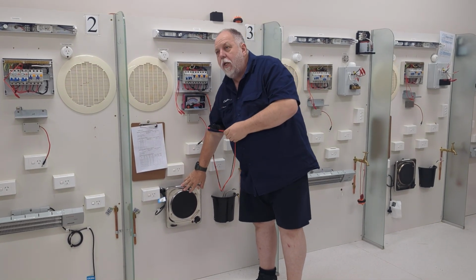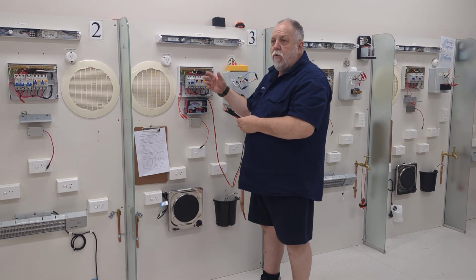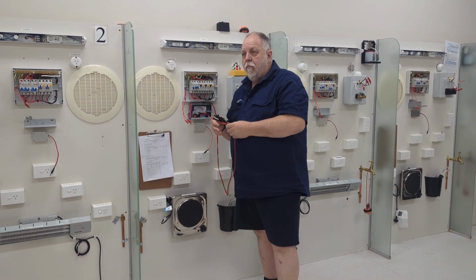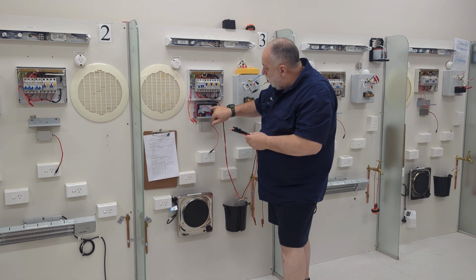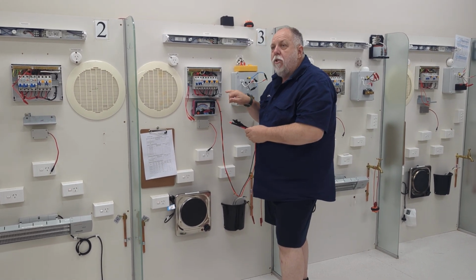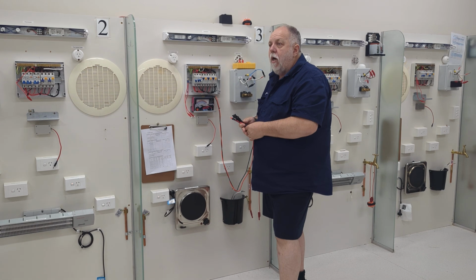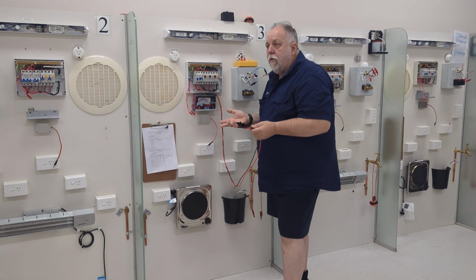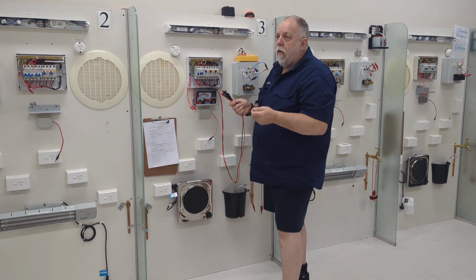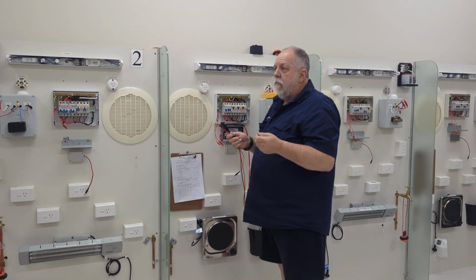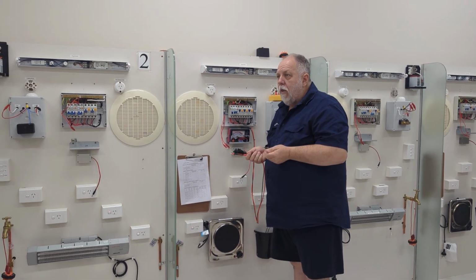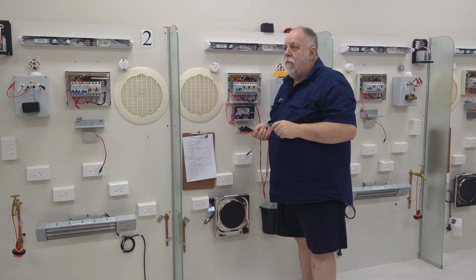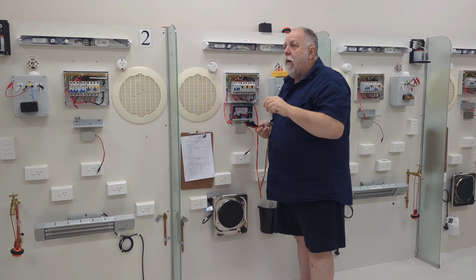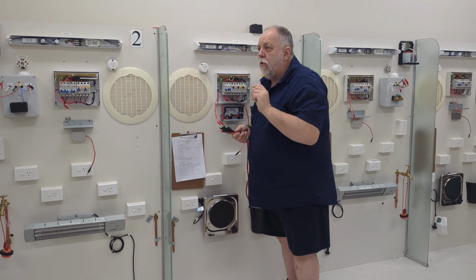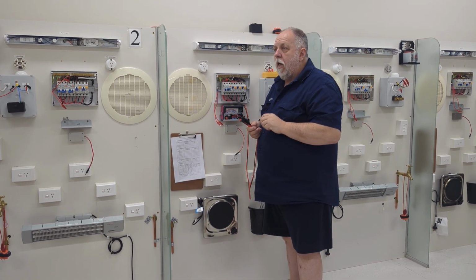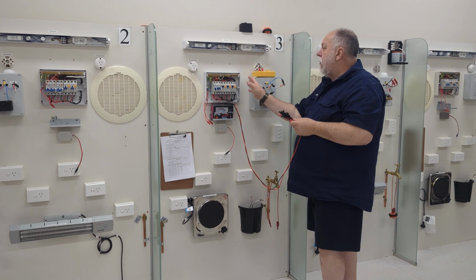Any heating elements, metal sheath heating elements like this one, hot water service or stove, they're 10,000 ohms. Be wary, the 0.01, if you look on this meg, sits just above the 0. That's 10,000 ohms. 0.1 is 100,000. I've had people go in the SWP and they've got to read out the reading and they go, oh, it's 0.1 of a minimum reading. Okay, he's writing down 100,000. You probably think it's 10,000, but I always say don't use the 0.01, just say 10,000. Okay, all right, 0.5 is a fail.